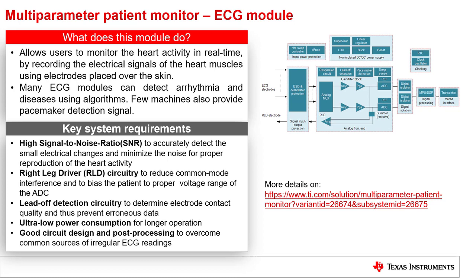Lead off detection circuitry, to determine electrode contact quality and thus prevent erroneous data. Ultra low power consumption for longer operation. Good circuit design to overcome common sources of irregular ECG readings. Apart from these system requirements, isolation has to be taken care of for patient safety purposes. A common block diagram for such ECG modules is also shown in this slide.